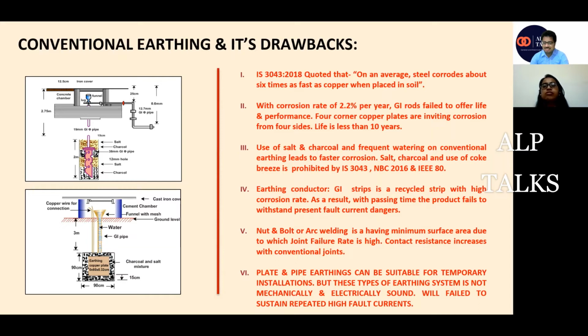Also, the corrosion rate of GI is very much higher as compared to copper. It is 2.2% per year, so it also decreases the life of our earthing conductor. Using it with salt and charcoal, be it plate earthing, also increases the corrosion in our earthing system. So now, as I have already told you, the standards prohibit the use of salt and charcoal for the earthing system.